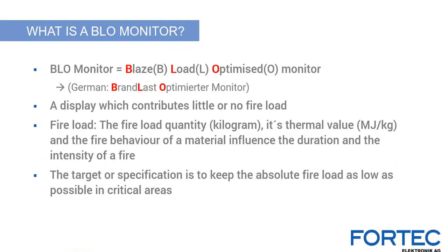Fire load is defined by the quantity in kilograms, its thermal value in megajoules per kilogram, and the fire behavior of the material — all of which influence the duration and intensity of a fire. The target of fire protection is to keep the absolute fire load as low as possible in critical areas.